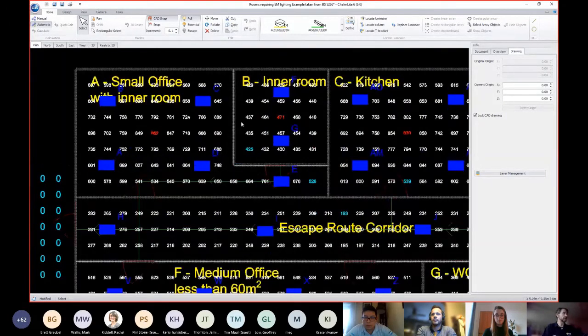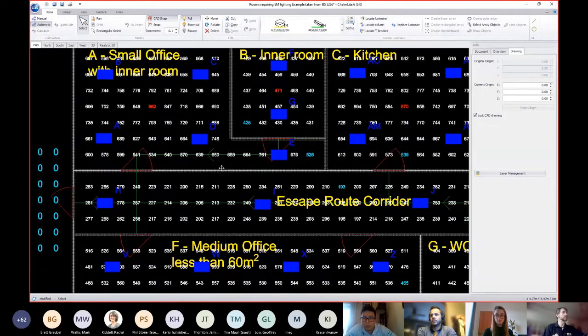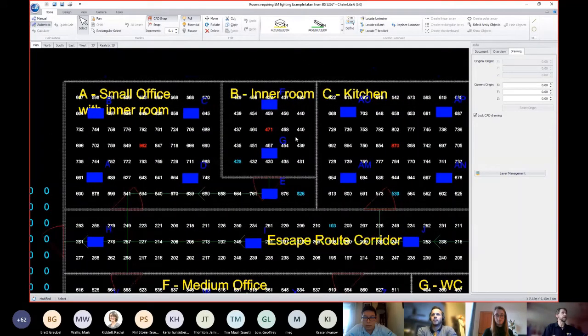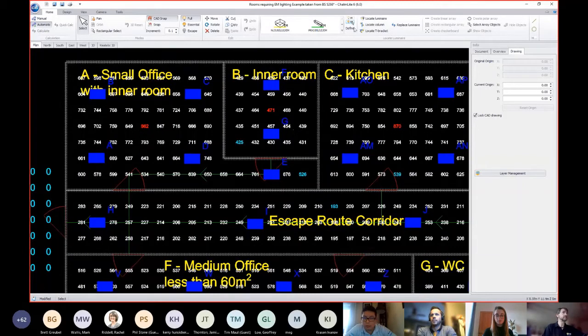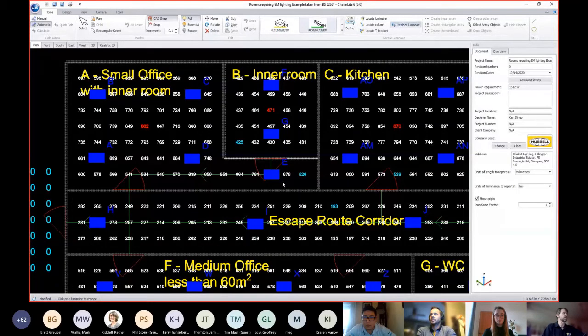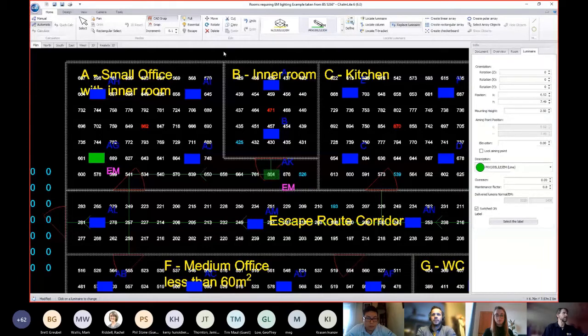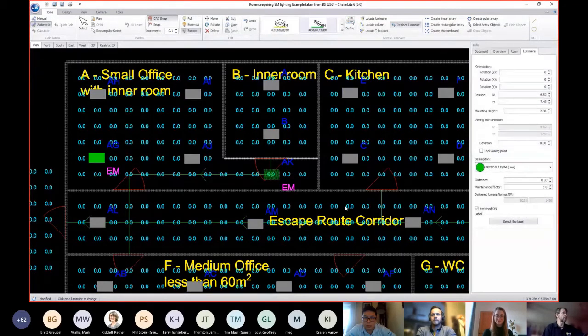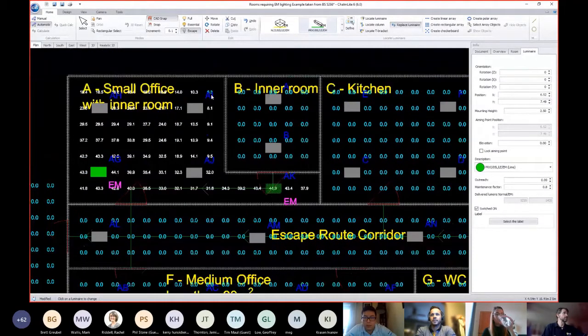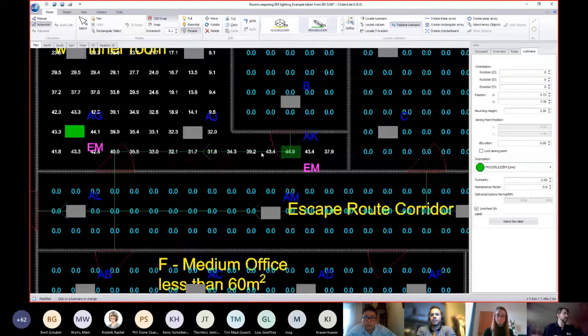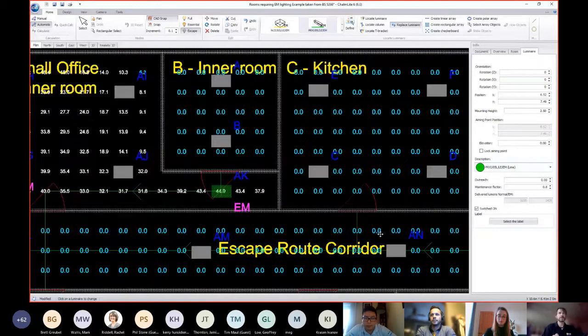So here's a room, this little small office. It's less than 60 square metres, so technically it doesn't need an emergency fitting according to the standards. However, it does form part of the escape route for this little inner room here, so we absolutely do need to light this to half a lux. So I'm going to change some of these to emergency lighting products when I find them. There we go. So we're going to replace that luminaire there, and that luminaire there, and I'm going to switch to escape level so we can see. Okay, so now we can see in this room, small office, our minimum is over here. We've got 6.3. We're lighting the escape route to the door. Okay, great. So let's step through the next one.